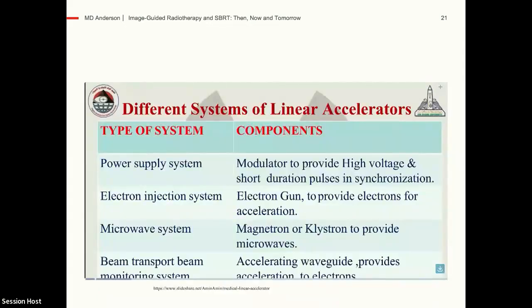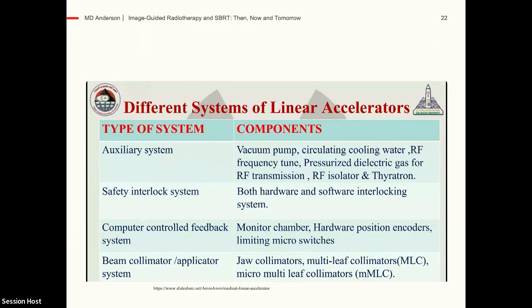There are different types of system components we utilize to get that beam. You have the power supply system, which includes a modulator to provide high voltage, short duration pulses, and synchronization. You have the electron injection system, which is that electron gun I discussed, a microwave system, either a magnetron or klystron, and a beam transport system, which is that accelerating waveguide. After that you have an auxiliary system, but most importantly, safety.